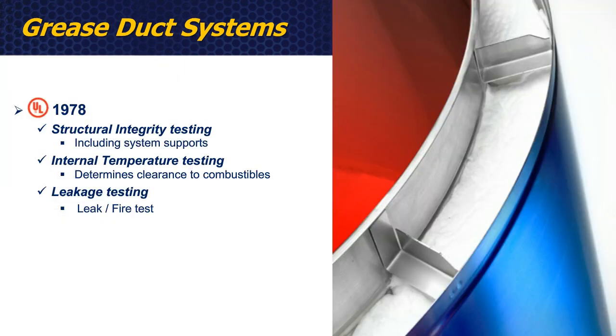So under UL 1978, amongst all the tests you go through, it would go through a structural integrity test and make sure all the supports of the vertical duct and hangers for the horizontal would all be included in that testing to make sure they can withstand the weight of the duct and withstand a potential grease duct fire as well. An internal test would also be done with temperatures considered to be as high as a grease duct fire to determine what our clearance to combustibles would be. And then I think really important to note that UL listed products will go through an actual leakage test with UL. UL physically is going to assemble your ductwork and basically create a grease duct fire inside of your system. So your product is going to be subject to the temperatures, the strains of thermal expansion, the liquid grease inside of it, and ensure that all the joints, construction and such can withstand an actual grease duct fire.